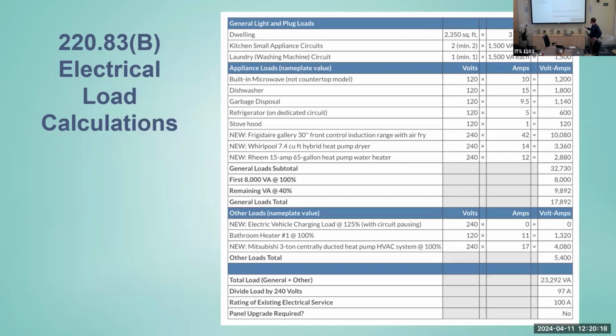But the code allows us to take the first 8,000 of that and count it as 100% coincident. The remainder we can multiply by 40%, again because we're not using everything all the time. That comes out to about 17,800.